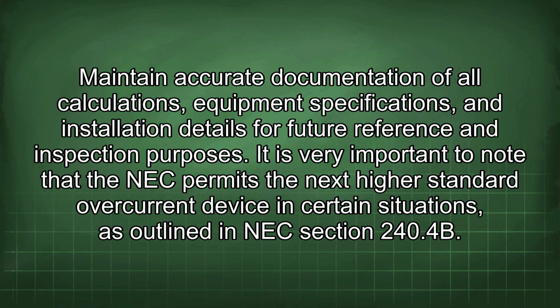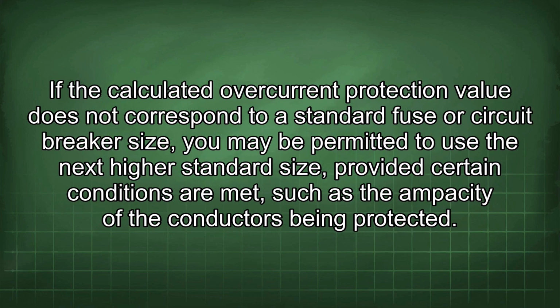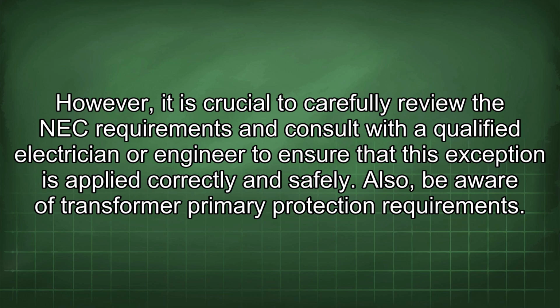It is very important to note that the NEC permits the next higher standard overcurrent device in certain situations, as outlined in NEC Section 240.4(B). If the calculated overcurrent protection value does not correspond to a standard fuse or circuit breaker size, you may be permitted to use the next highest standard size, provided certain conditions are met, such as the ampacity of the conductors being protected. However, it is crucial to carefully review the NEC requirements and consult with a qualified electrician or engineer to ensure that this exception is applied correctly and safely.